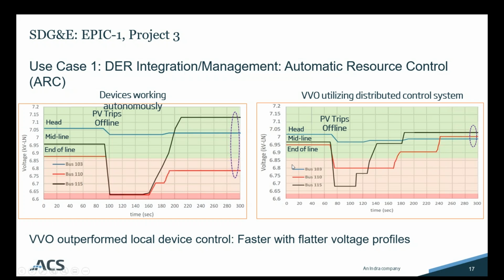So then compare that to using the distributed VVO approach from the ACS system. And first we can see in the steady state condition, the voltages are much closer, thus having a much tighter and flatter voltage profile. But then also when that large PV trips offline, you can see that the voltages react far quicker than in the previous example. And then finally, you can see that the voltages are flattened and very tightly integrated, and this is using a model as a whole as opposed to just seeing certain points on the system. By using the model of the entire feeder, you're able to optimize it far better than just the controls working autonomously.